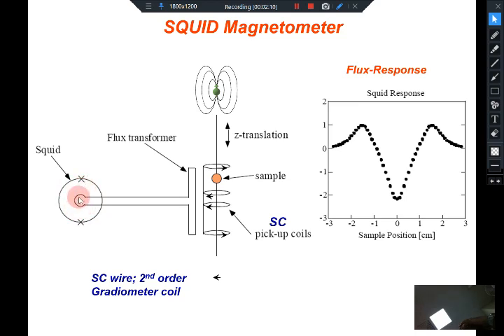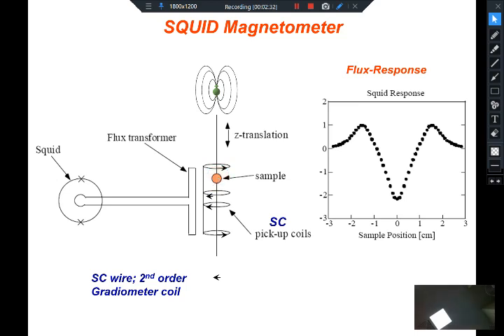Whatever the flux is, it tells you how much current is present. The field generated inside the SQUID loop is proportional to how much current is flowing in this region, and this current flowing through this loop is proportional to how much current is induced in the coils through which the magnetized sample is moving. Hence you can actually calibrate and tell how much is the magnetization of the sample. In this way, very weak magnetization samples which have very low magnetic fields around them and introduce very low currents in these pickup coils can be detected using the SQUID magnetometer.